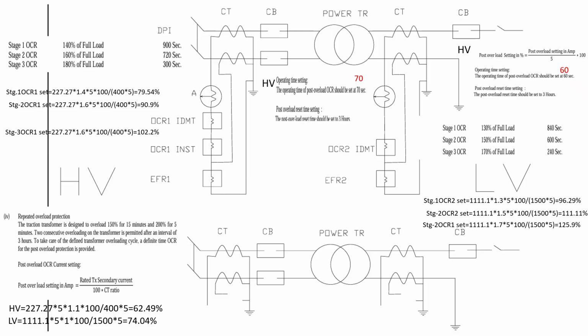So these are all MB2 CTs. Both are connected in series, and it helps not only the instantaneous but IDMT as well as restricted earth fault. IDMT permits the overload for a particular time. Slowly, if the time reaches that threshold, then the CB will trip.